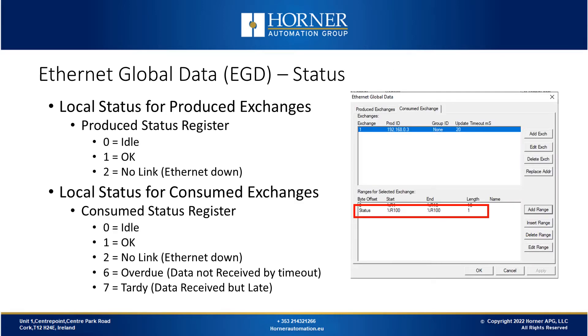Here are the details on what you get in your status register both on the produce side and the consume side. On the produce side the only information is everything's working normally, which is status 1, or there's no link or the Ethernet is down, which is status 2. On the consume side similarly you have status 1 for normal and status 2 for no link. But in addition, if the timeout you set is exceeded but the data still comes in, it's known as tardy, which is status 7. If the data doesn't come in at all and your timeout expires, it's overdue, which is status 6. If you have status 2 or 6 then you have an issue and you need to take corrective action.